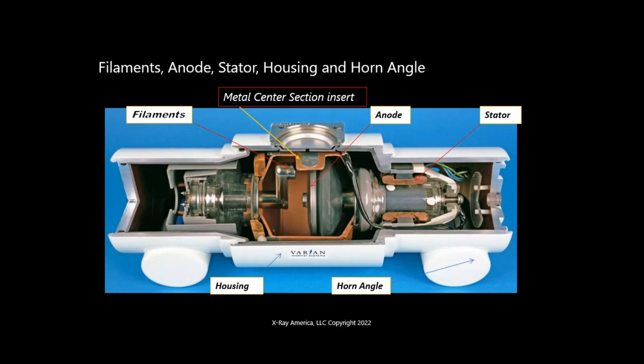I'd just like to mention, when you talk about anode grounded CTs, the oil is for a different application, right? In some typical X-ray tubes, the oil acts as an insulator against the housing, the ground. So that's why dielectric strength is very important. This is the whole point of processing oil. When you have an anode grounded tube, the oil is for cooling purposes, not for insulation. You can actually have air inside your tube without having arcing. This is why you get those artifacts mostly in the GE CTs, because you can get air trapped in there and it's not a big deal. But when you talk about a Siemens CT, the oil acts as both, not just for cooling but as an insulator. And that's why dielectric strength is a big problem.